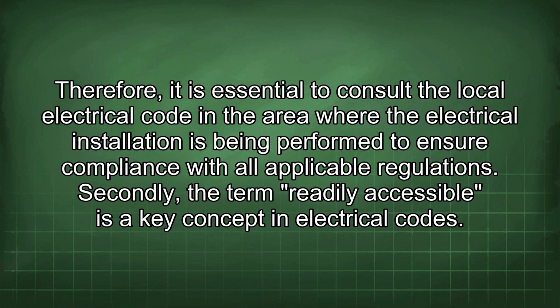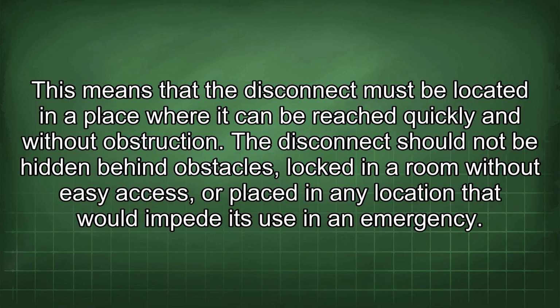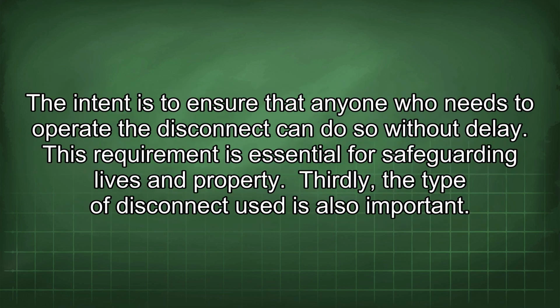Secondly, the term "readily accessible" is a key concept in electrical codes. This means that the disconnect must be located in a place where it can be reached quickly and without obstruction. The disconnect should not be hidden behind obstacles, locked in a room without easy access, or placed in any location that would impede its use in an emergency. The intent is to ensure that anyone who needs to operate the disconnect can do so without delay. This requirement is essential for safeguarding lives and property.